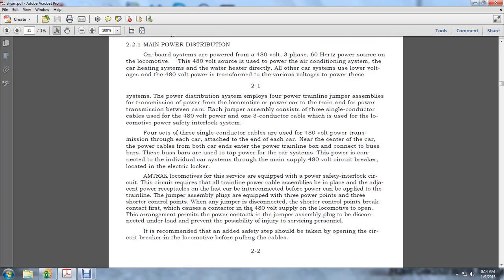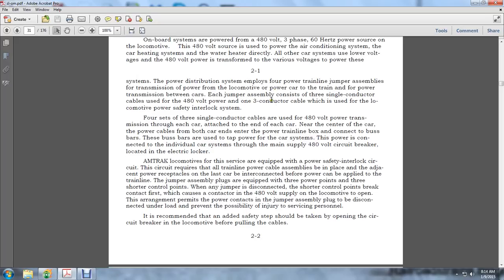The Amtrak locomotives for this service are equipped with power safety interlocking circuits. The circuits require that all train power cable assemblies be placed in adjacent power receptacles on the last car before power may be allowed on the train line. The jumper assembly plugs are equipped with three power points and three shorter control points. When a jumper is disconnected, the short control points break contact first, which causes the 480 volt supply contactor on the locomotive to open. This arrangement permits the power contacts in the jumper assembly plug to be disconnected unloaded, to prevent the possibility of injury to servicing personnel. It is recommended that added safety steps be taken by opening the circuit in the locomotive before pulling the cables.